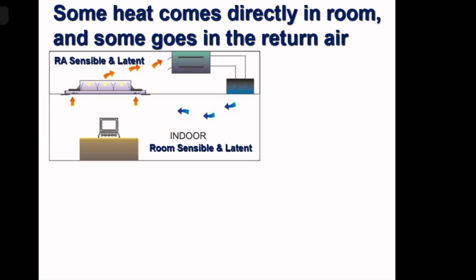So if the mixing of air inside the room is proper, anywhere in the room you will get 24 degrees centigrade. But if you take the supply air blast directly, then it is not 24 degrees centigrade, it is 12 degrees centigrade. You will feel colder. So when I suggest anybody install an air conditioner in his bedroom, I say don't put the air conditioner over your bed or over your head, because you will get a direct blast of 12 degrees centigrade air. So you will feel colder. Put it away from your bed so that the air picks up all the heat of the room and becomes 24 degrees centigrade.